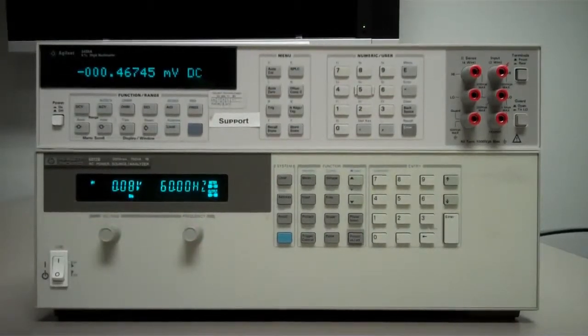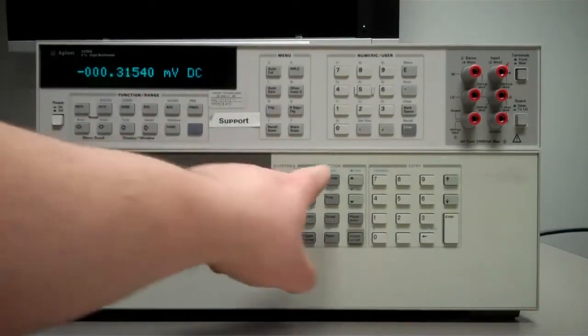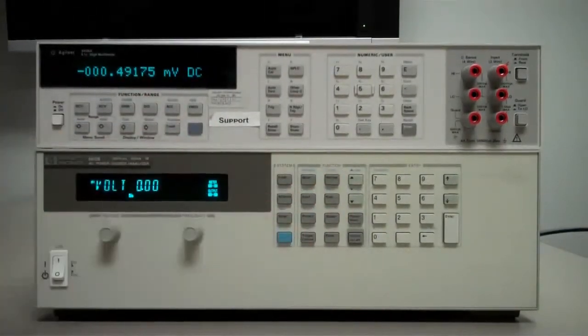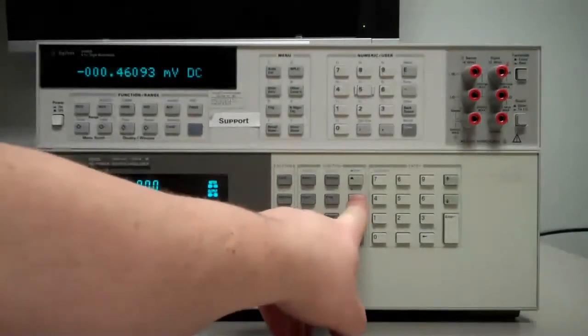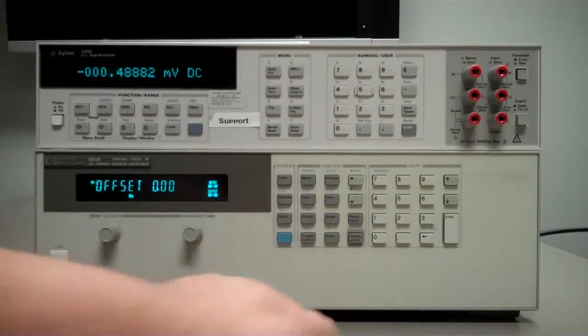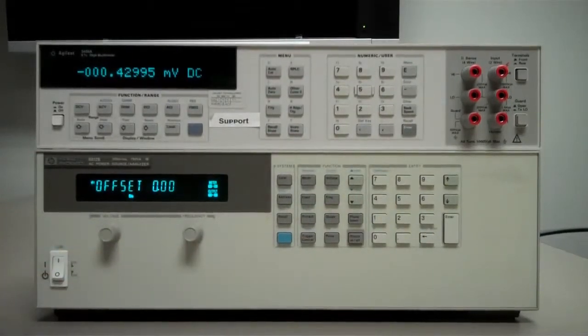The next thing we're going to do is set the voltage. Hit the voltage key right here and that brings up the voltage menu. We're going to scroll down using these arrow keys until we see offset. Right now the offset is set to zero.